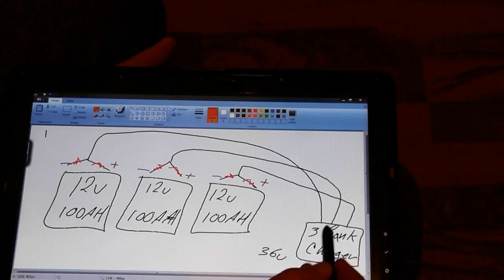I had a friend who had a 3-bank charger, and it violently blew up. After looking through it, it appears that internally something happened in the charger that caused two of the grounds to actually connect. I verified it with an ohm meter, and they were dead short. Typically they're supposed to be isolated, but something happened in the charger. Of course, it was all potted and you couldn't really get it open, but with an ohm meter I could verify that two of the grounds were actually dead short.